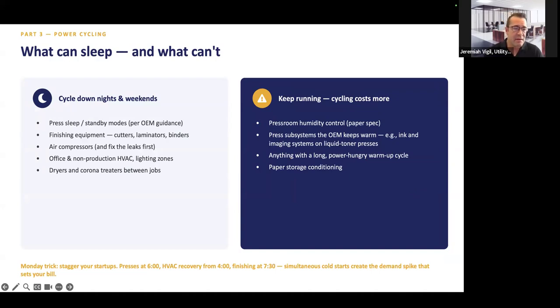On the left side, we have cycle down nights and weekends - here's what you probably can put to sleep in your printing room. Presses can go to standby modes; always check OEM guidance and manufacturer recommendations on what you can and can't do. Laminators, binders, cutters, and other finishing equipment don't necessarily need to be on over weekends or off hours. Air compressors are something you should always look at - fix the leaks first, but once fixed, you can cycle those down on weekends too.